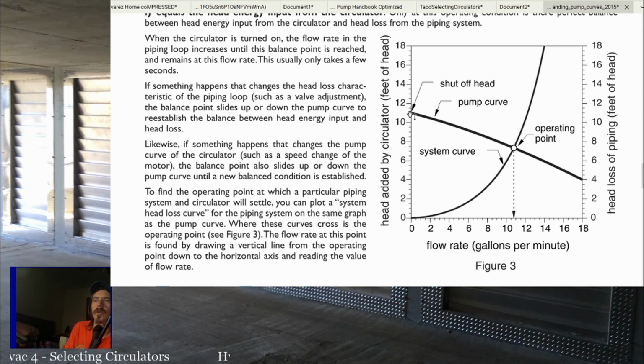So once you get over 10 feet or 11 feet of head on a 007, it basically won't pump anymore. Okay. It's going to freewheel at that point because you're just over more head than it can produce. That pump can basically only create about what, 12 feet of head. It can basically only create about 5 psi, say, and you're over 5 psi. So the pump can't create more than 5 psi worth of head pressure. So anything over that, it's just not going to do anything. All right, that's the shutoff head. It's just going to deadhead basically.